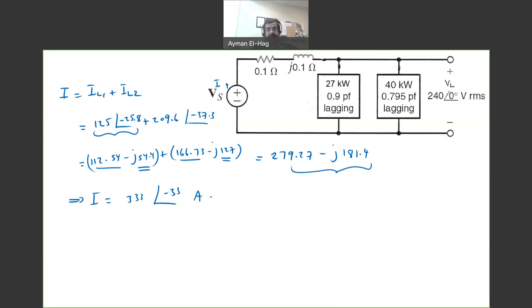Now, once we found the total current, then you want to find the power loss. Your power loss is equal to the I square times R, which is equal to 333 square times the 0.1, and this will give me approximately 11.1 kilowatt. So, this is your power loss between the supply and the load.